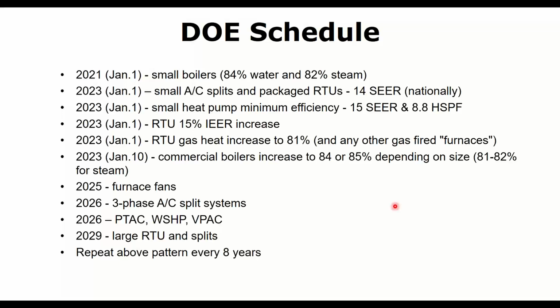So right now we're talking about the Department of Energy schedule - the rules that the manufacturers that make things have to comply with. The most recent one was last year: small boilers, 299,000 BTUs and under, so residential and light commercial boilers, bumped up their efficiency. The minimum efficiency went from 82 to 84% for hot water, and up to 82% for steam.